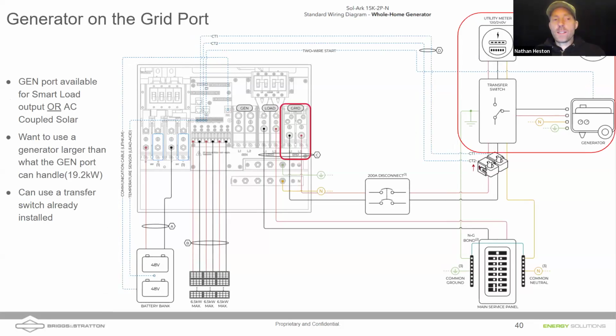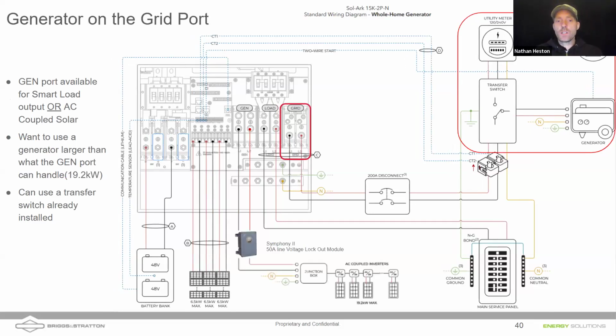And so in this case, we talked about programming already. In this case, where we've got the generator connected to the grid port, you still get the 2-wire start functionality there. It's just going to be based on a different column. Also, if you have the generator on the grid port, you can still utilize AC coupled solar. Now, you wouldn't want that solar powering and trying to backfeed the generator, right? So what can we do about that, Daniel?